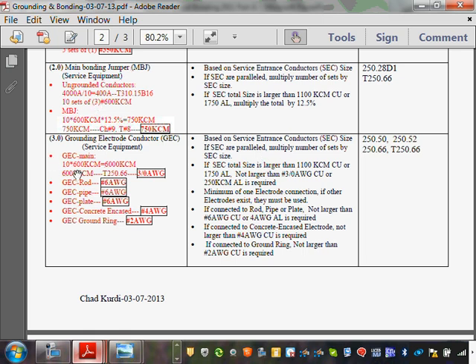So long story short, you take the same calculation, 10 sets multiplied by 600. These are the ungrounded conductors, the phases, and that gives you 6,000 kcmil. You take the 6,000 kcmil to 250.66, and that gives you 3 aught. The NEC book says stop right here at Table 250.66. You do not need to go higher than 3 aught for the grounding electrode conductor. Any comments, guys, about that one? 3 aught. Why did I multiply by 10? Because I have 10 sets.